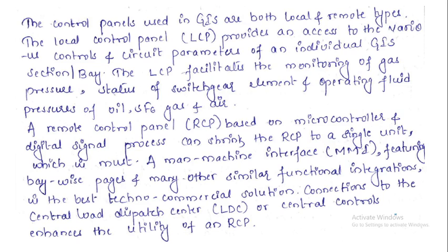The control panels used in GIS are both local and remote types. The local control panel provides access to the various control and circuit parameters of individual GIS sections or the bay. The local control panel facilitates the monitoring of gas pressure, status of the switchgear element, and operating fluid pressures of the oil, SF6 gas and air, etc. So locally we can control all the parameters.